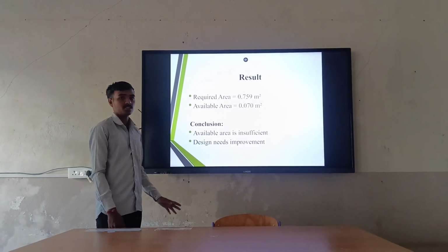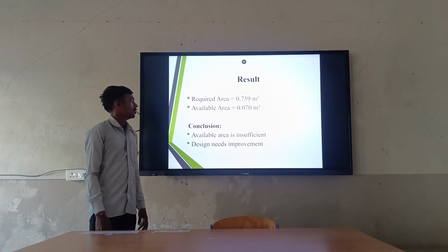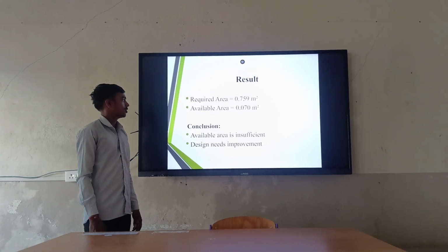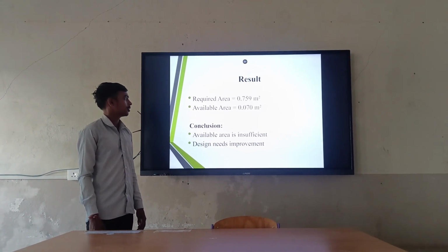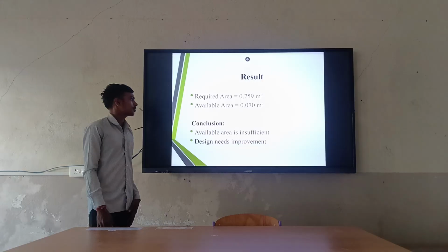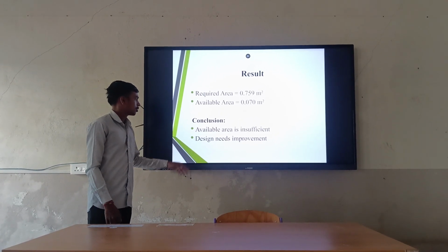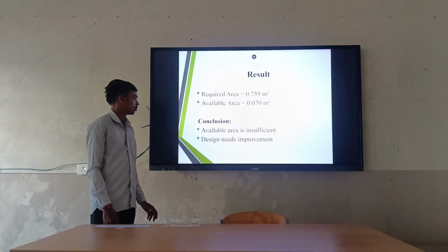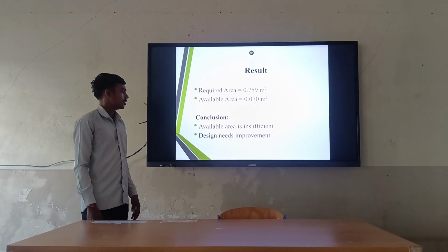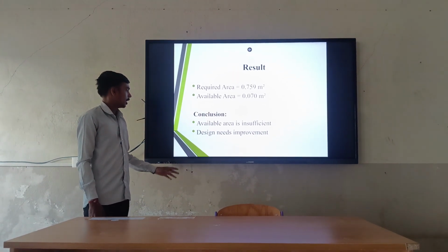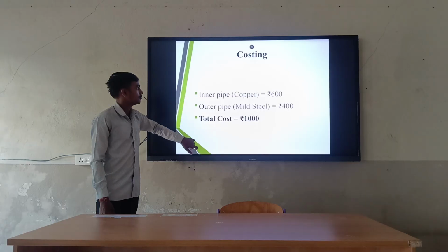Next slide is result. The required area is 0.759 meter square, and available area is 0.070 meter square. Conclusion: available area is insufficient, and design can be improved.